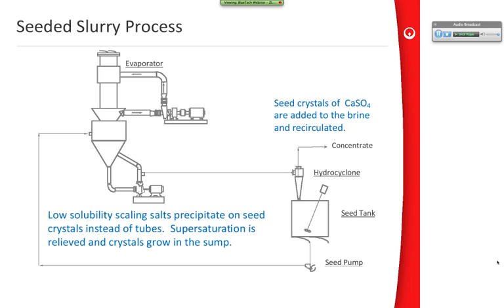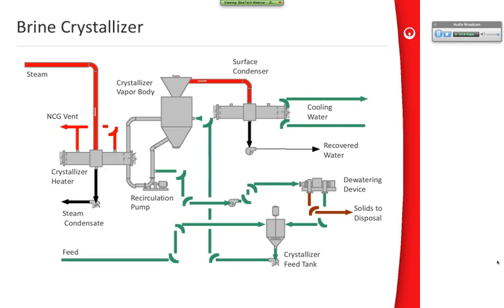The idea is that like likes to precipitate on like, so we put a lot of crystals into the brine that's circulating around. The low solubility salts preferentially precipitate on the seed crystals rather than on the heat transfer surface. That's why it's important to have a large sump in the brine concentrator, because that's where supersaturation is relieved and the crystals grow. If you have a small sump, then typically the crystals will grow on the heat transfer tubes.